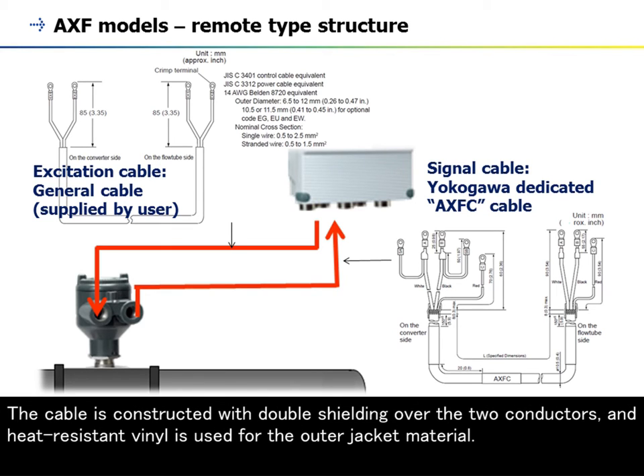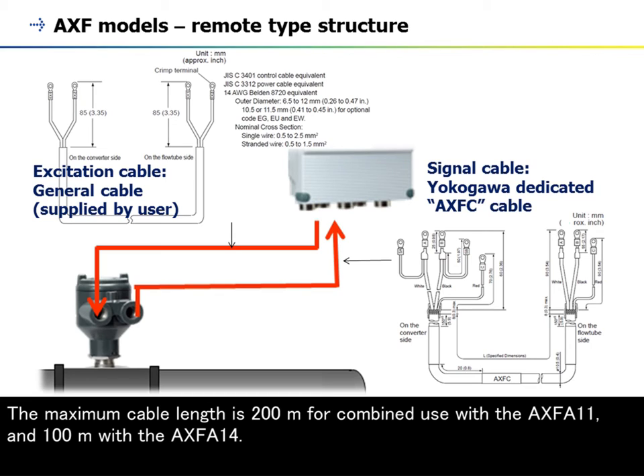The cable is constructed with double shielding over the two conductors, and heat-resistant vinyl is used for the outer jacket material. The maximum cable length is 200 meters for combined use with the AXFA11, and 100 meters with the AXFA14.